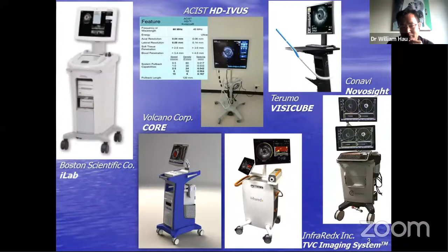And when it comes to IVUS catheter technology, currently we have two different types, the solid state and the mechanical. The mechanical type of IVUS catheter consists of one single transducer located at the distal end of a motor driving cable. And I call this catheter a high frequency catheter because the frequency goes up to 60 megahertz. It rotates 30 rotations per second to capture the IVUS images. But the problem with this kind of IVUS catheter design is that it has an air space, it can trap air. That's why we need to flush to get rid of air bubbles. If there's an air bubble inside, we cannot get a good IVUS image.